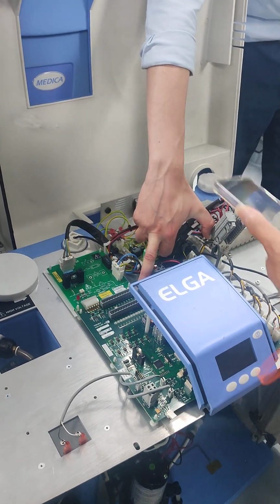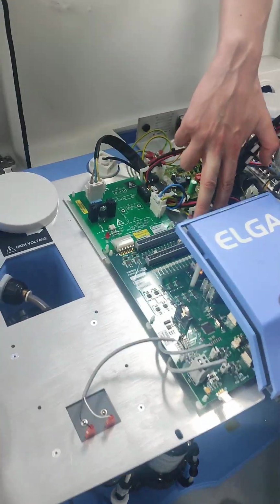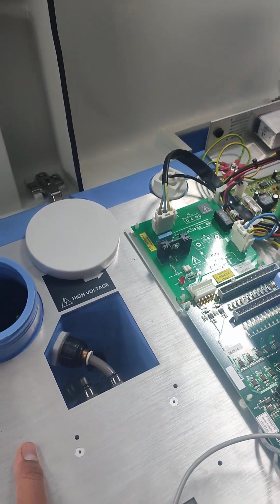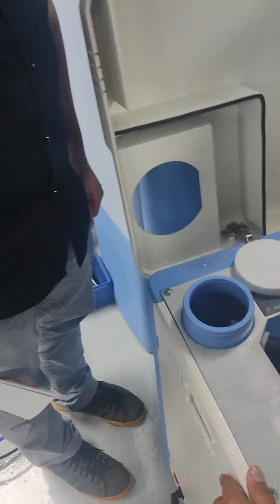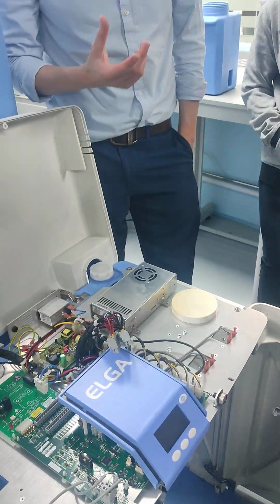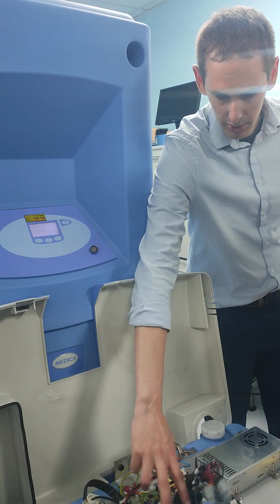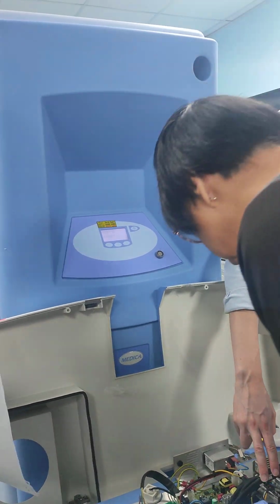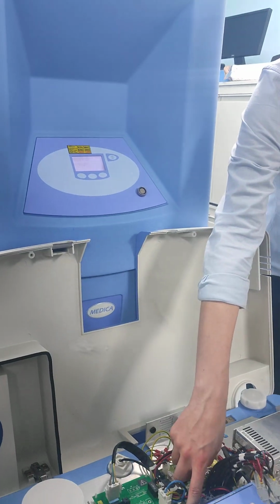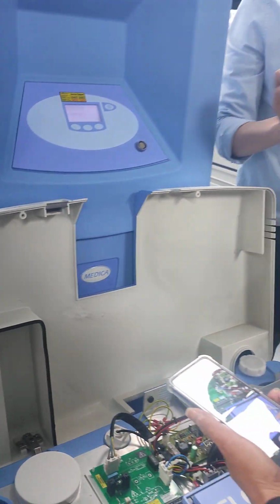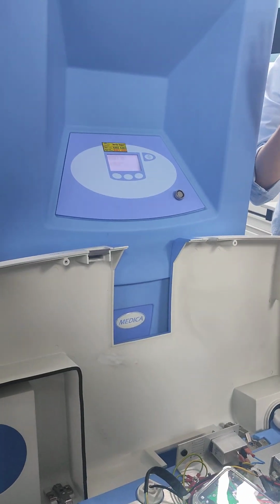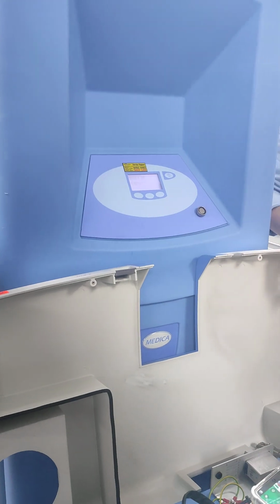It's the same 5 amp fuse. The other two fuses are to protect the motors, basically the pump circulation and the inlet solenoid valves and those kind of things. The one for the recirculation is often the one that will fail - if anything's going to fail, it will often be that one.